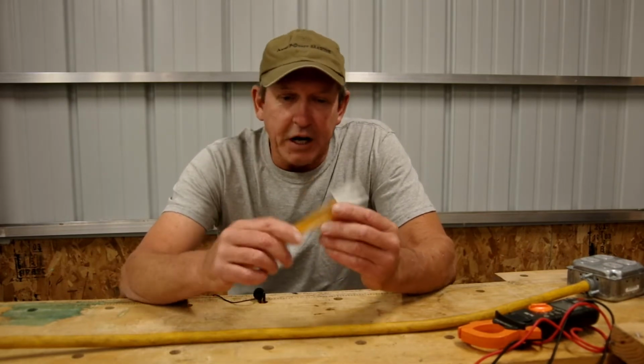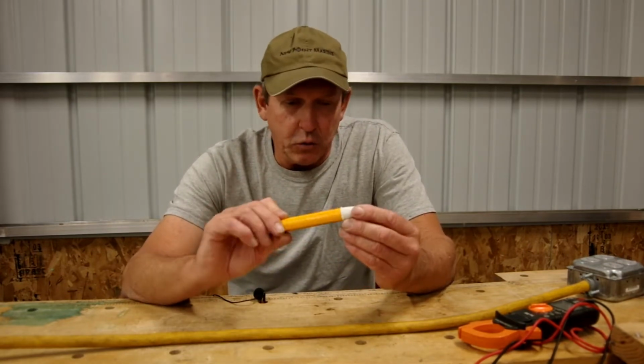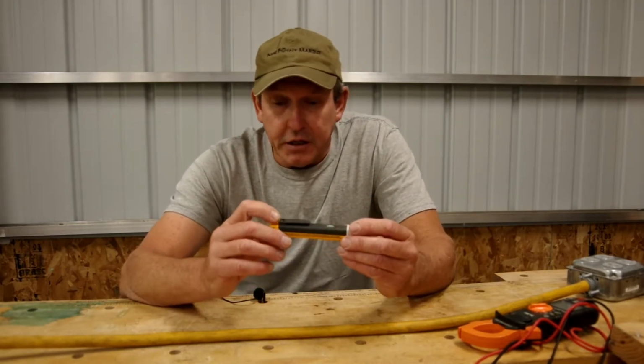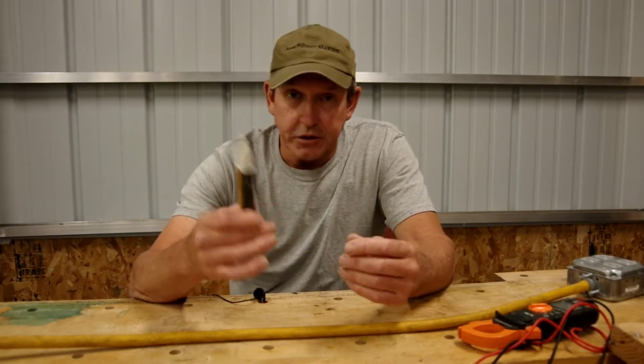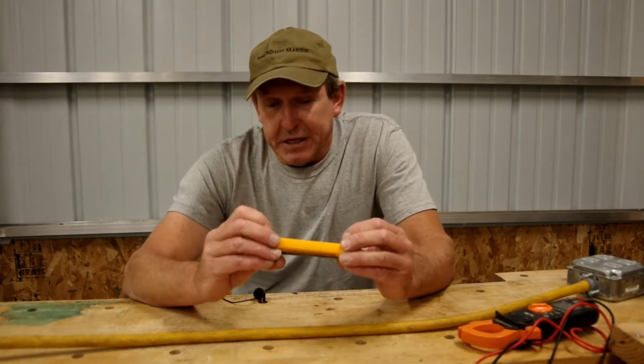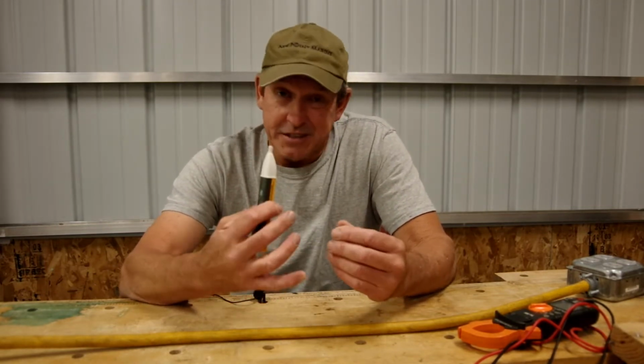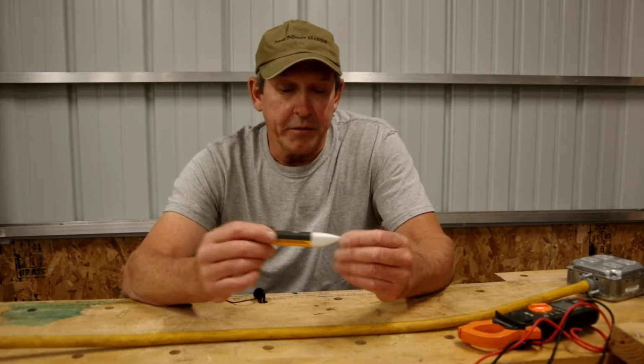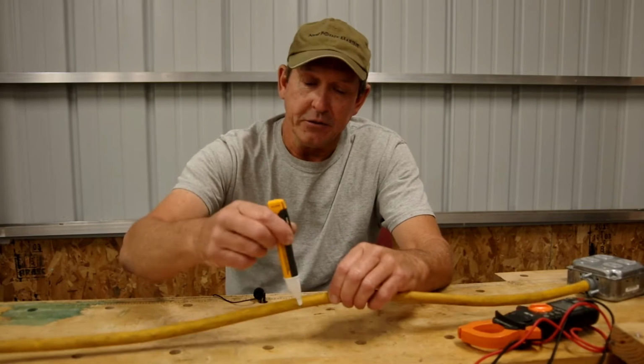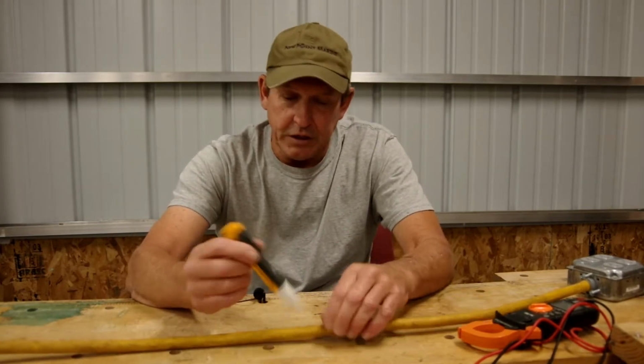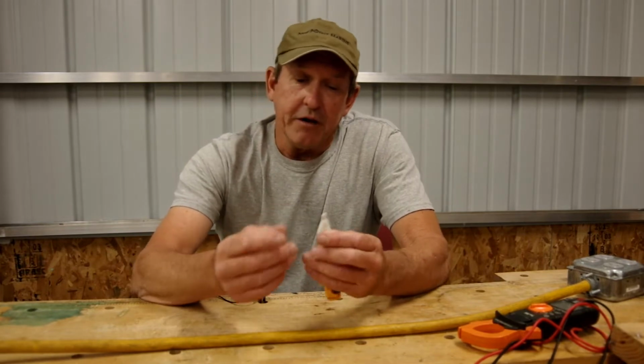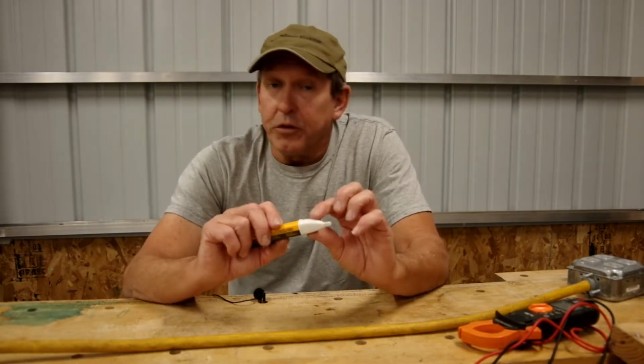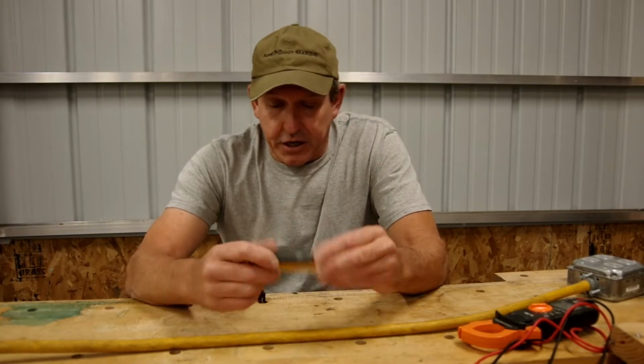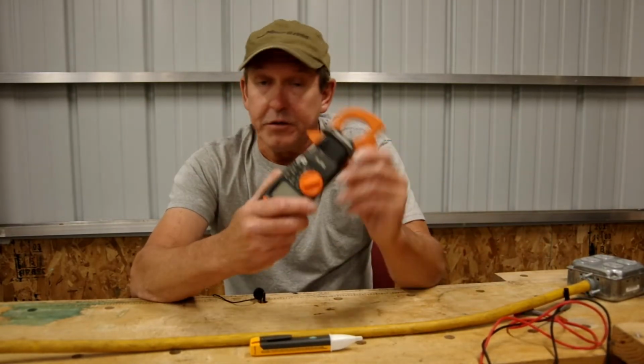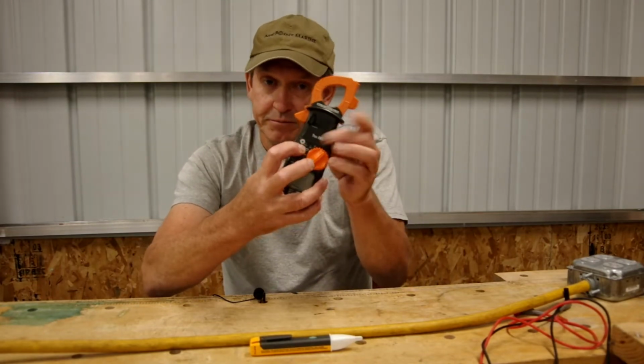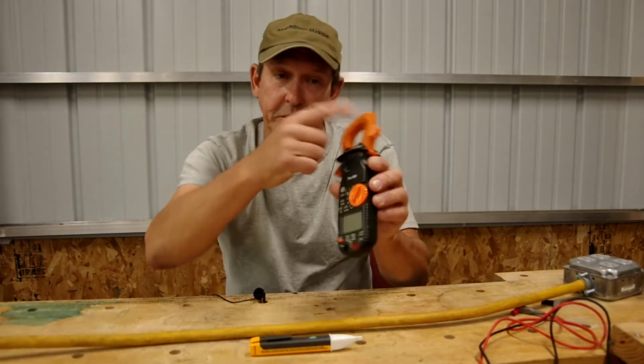Okay, so non-contact voltage detector, a very affordable little tool. It comes in a pretty big variety. You can find them dirt cheap, or you can go for more expensive models. One of the biggest differences between them is probably the sensitivity. Some will sound an alarm if they just get close to a conductor, while some need to be directly contacting it, and are a little less sensitive. Some have additional features, like one I saw with a cool little flashlight built in, which is a nice touch. My multimeter actually has one built in, so I have a non-contact voltage detector built into my multimeter, which is a nice touch.